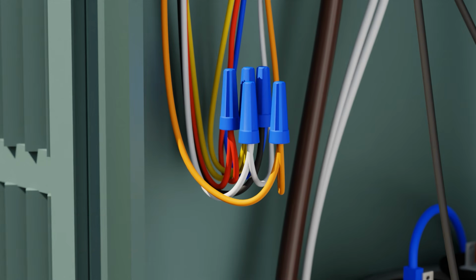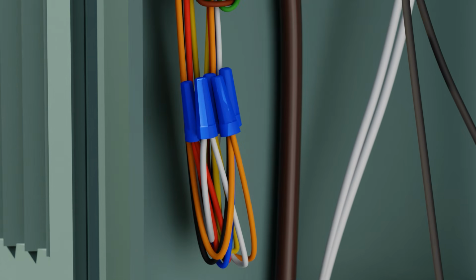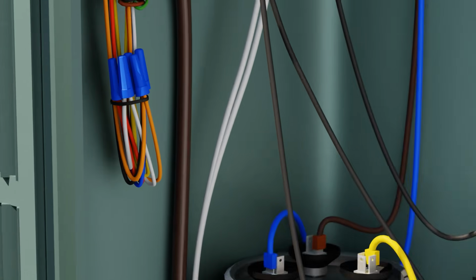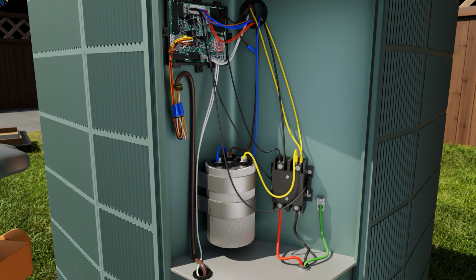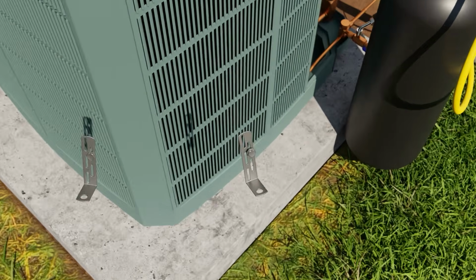Keep the wire nuts pointed upward to keep moisture out of the wire nut, and put a zip tie around them as shown to hold them in place. Wire routing varies from system to system, but always keep your wires neatly routed, leaving appropriate levels of excess wiring, and not leaving any of your connections in tension, meaning where they want to pull apart. With all of your conductors, always run them through appropriate grommets and strap them so that they won't chafe, creating a short circuit. Now we anchor down our condenser.